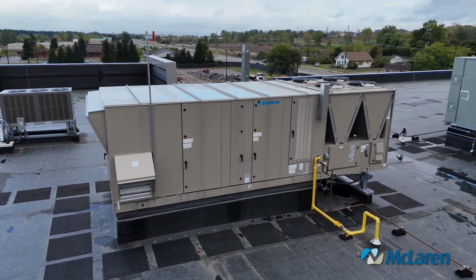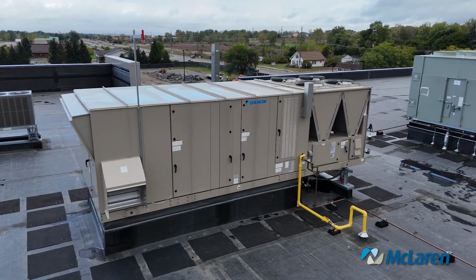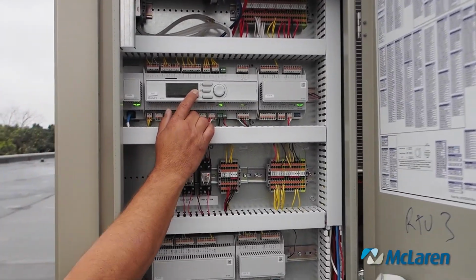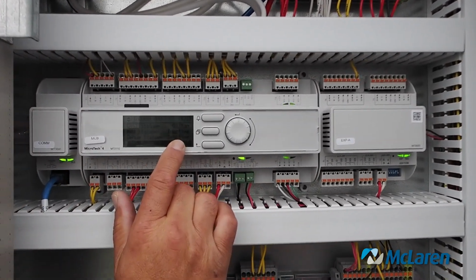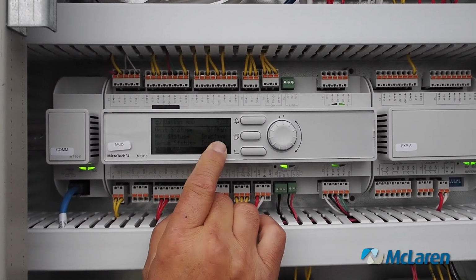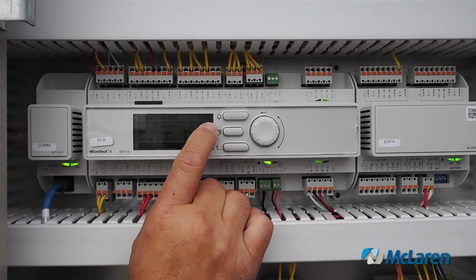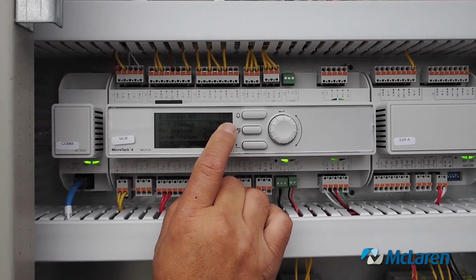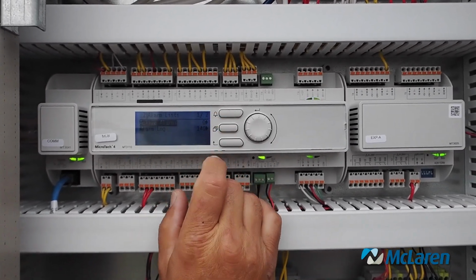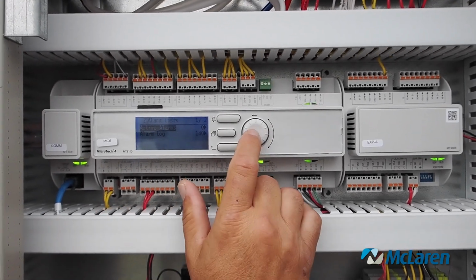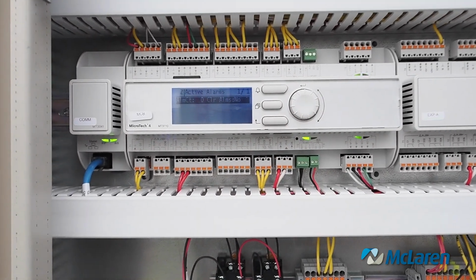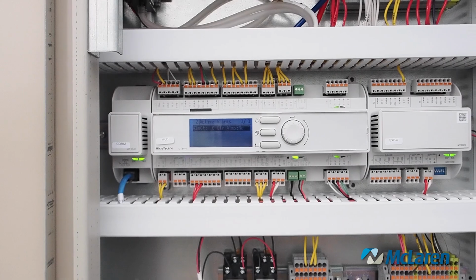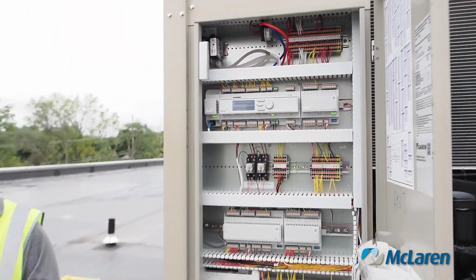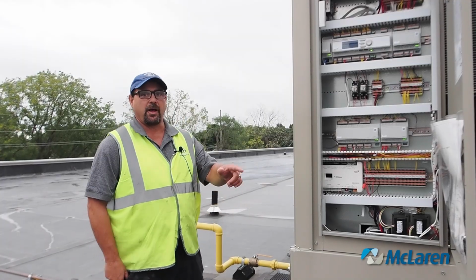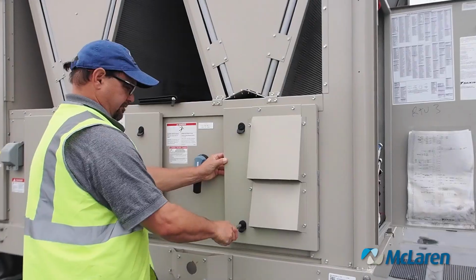I also want to point out really quick, if you could zoom in up here, there is an alarm menu on this item. If you have an alarm, the last digit will be an alarm bell blinking. To see what that is, you hit the alarm button, and then active alarms will come up, and then you hit enter. We don't have any alarms set currently, so there's nothing to show us, but that's where you'll find the current alarm. That's good for now. Let's move on to the next control panel.